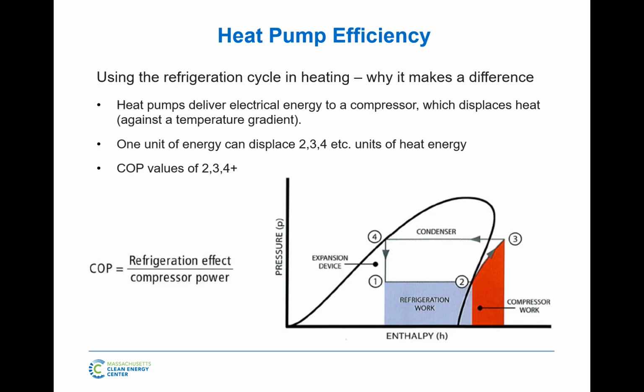So when we look at an air source heat pump system, remember the gas furnace is a 0.9, baseboard's a 1. The average COP of an air source heat pump is around 3. Now, unfortunately, COP is a full load value. That's the same thing as looking at the EER in cooling. When AHRI looks at it, they do the same thing: give me your unit, Mr. Manufacturer, and I'm going to see how many kilowatts of electricity you need to generate X amount of heat at different temperatures. But it's making that unit run as hard as it can at full load.